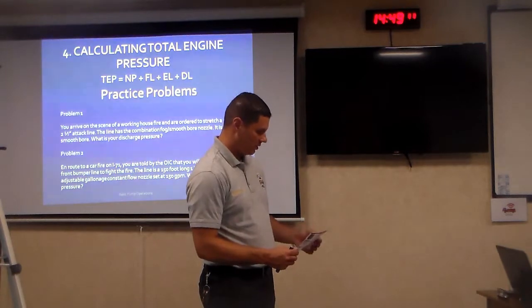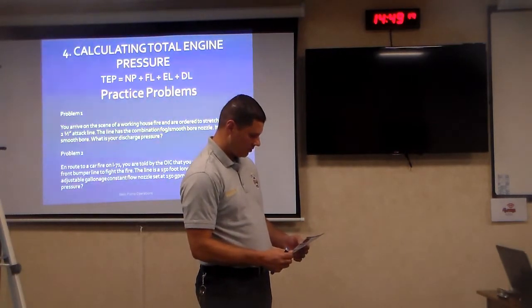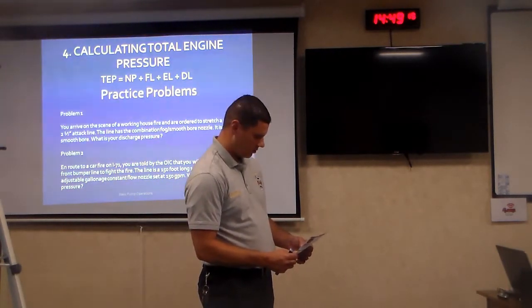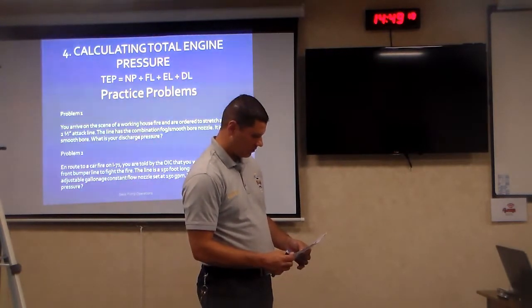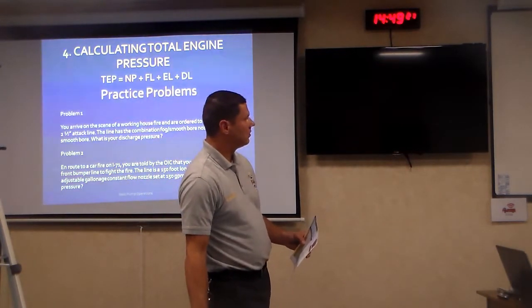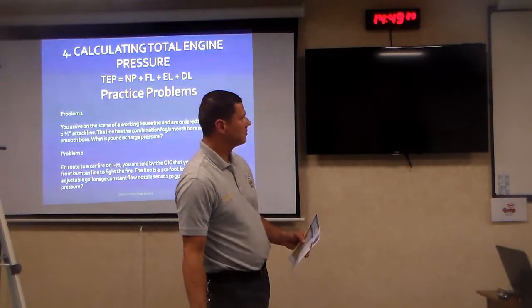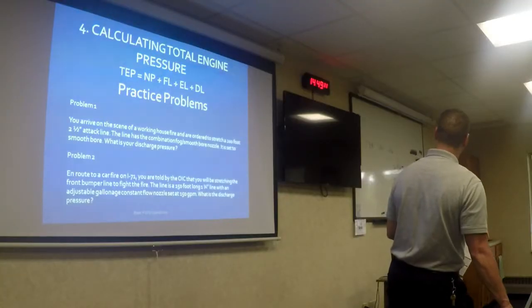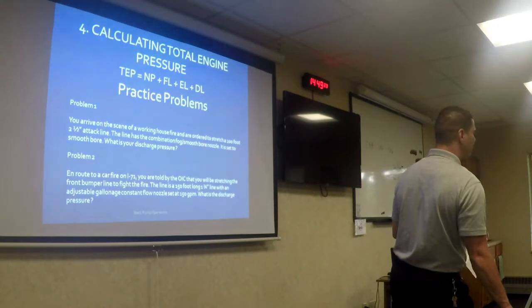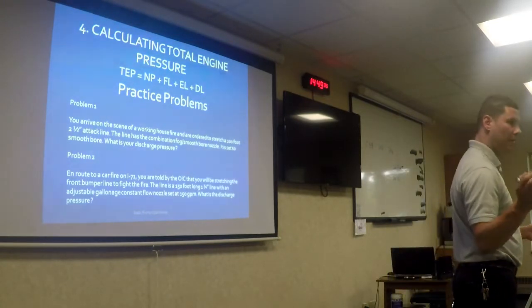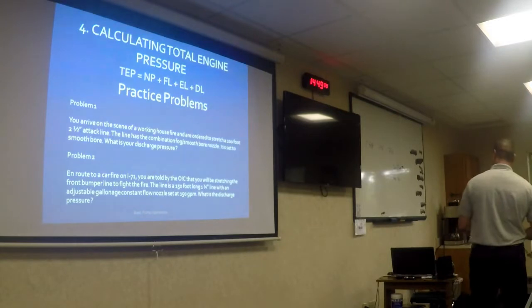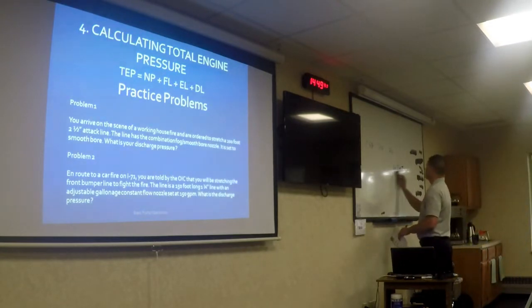Say around 78. 59. 68. 75 PSI. What size hose? 2.5? Yeah, 250 feet, 75 PSI. About 75. Oh, okay. Sorry, I did 200. Anybody else say anything different? Like right around there, 75? Right around there. Okay. 20 pounds of friction loss, 5 for the elevation, 50 for the nozzle pressure.